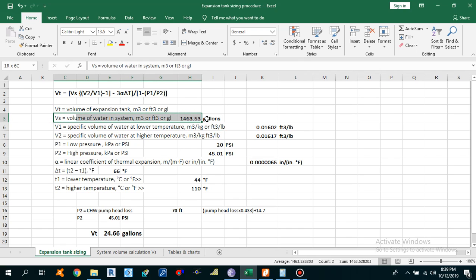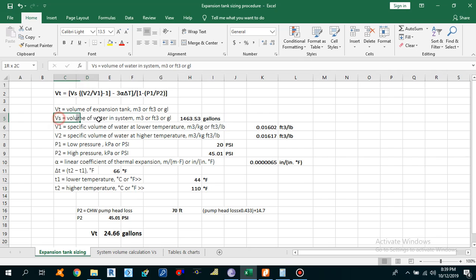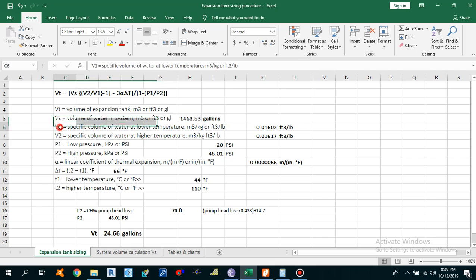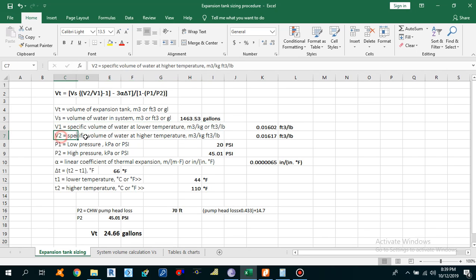Vs is the volume of the system — meaning all the pipes used in our project, all of the volume occupied by the pipes and equipment combined. It is the sum of all pipe and equipment volumes. V1 is the specific volume of water at low temperature, and V2 is the specific volume of water at high temperature.